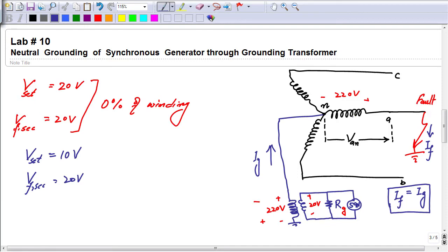Let's say the fault has occurred at 75% of the winding, somewhere here. So 75% of the voltage will be available between neutral and fault point. And how much will that be? That is 165. So 165 volt, and on the secondary side we get 15 volt. 15 volt is still above the pickup setting. The relay would operate for this fault. It means yes, if a fault occurs up to 75%, the relay can provide protection.